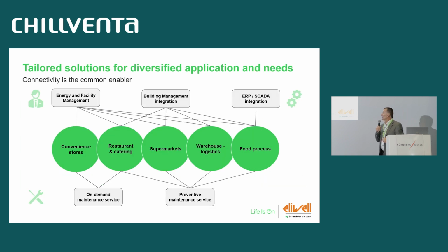We have to consider that different systems have different types of needs, because we may have sites that work on demand - typically small retail stores just call the technician when there's a problem. So they look for the problem, they call, and it gets fixed. In a larger system, especially supermarkets or industrial applications, there's more of a tendency to look for preventive maintenance and to have information in order to act in advance.